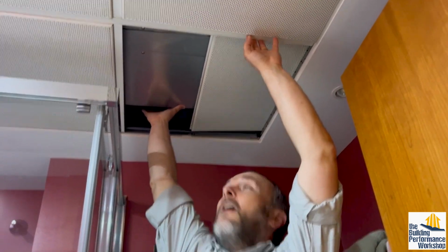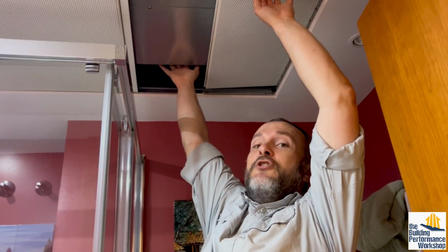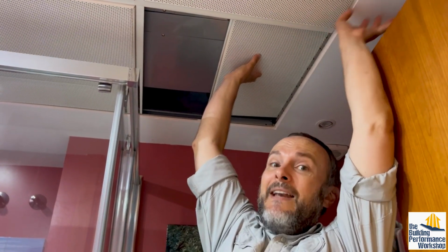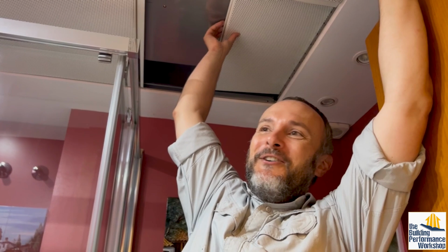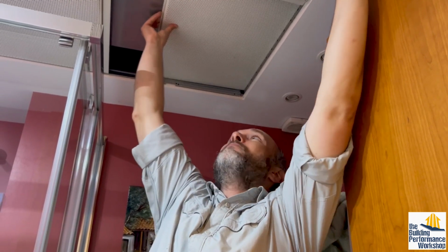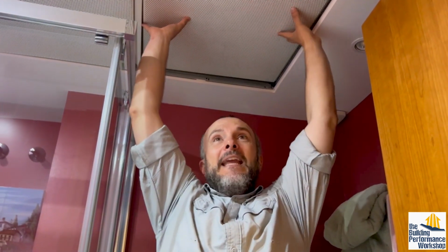So the filters are here. And I'm touching the filter right now. Now the filters in here, which I'll show you in a minute, are not super hardcore filters. So you're not going to be filtering out a lot of the dust that's coming from these ceiling spaces with those filters, which means that we're not mitigating the risk that came from using the ceiling as our plenum.